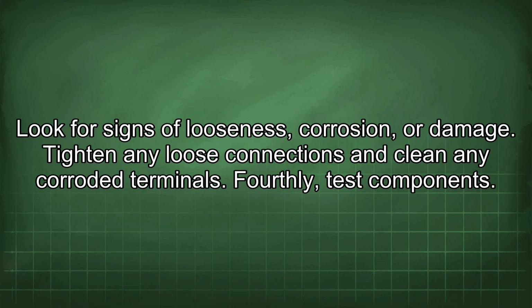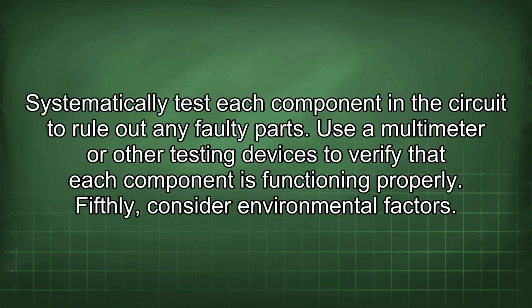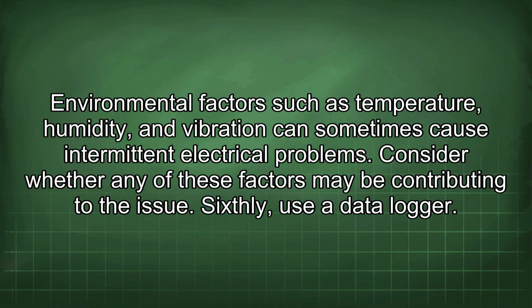Fourthly, test components. Systematically test each component in the circuit to rule out any faulty parts. Use a multimeter or other testing devices to verify that each component is functioning properly. Fifthly, consider environmental factors. Environmental factors such as temperature, humidity, and vibration can sometimes cause intermittent electrical problems. Consider whether any of these factors may be contributing to the issue.